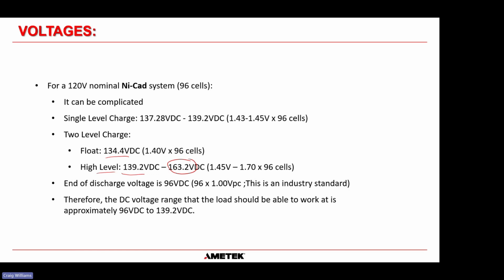People got fed up with doing this because it was a pain to implement in a plant setting. So what the battery manufacturers did was they actually oversized their batteries and went to a single level charge. They're saying that for a 96 cell system, the single level charge should be 137.28 to 139.2 volts DC. So it makes it easier for the end user to keep the batteries charged at a single level. Basically they oversize the battery because they know they're going to lose a little bit of capacity because they're not following this high level charge. But it's built into the design of the battery.